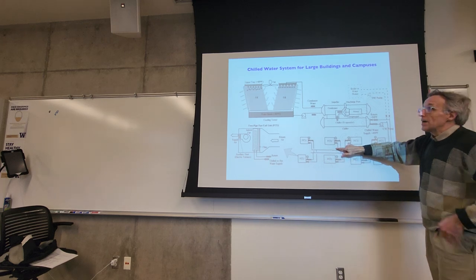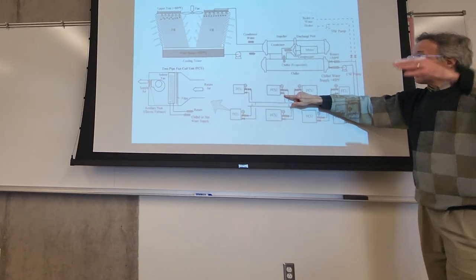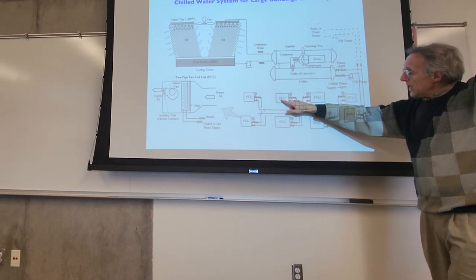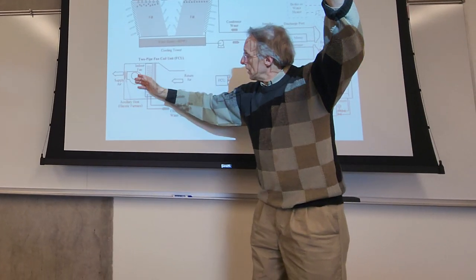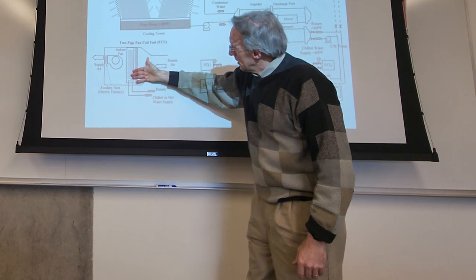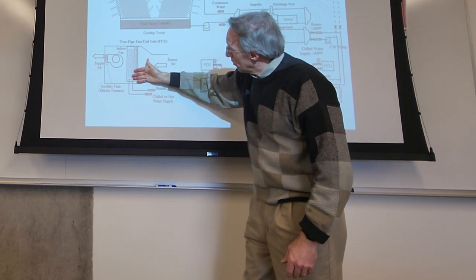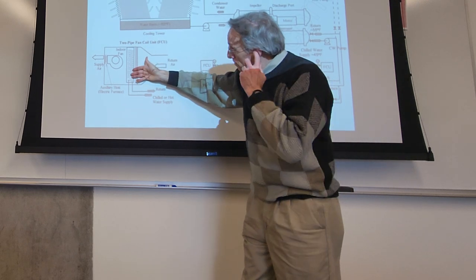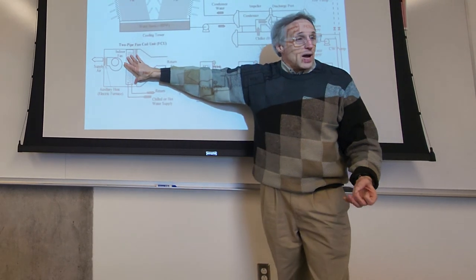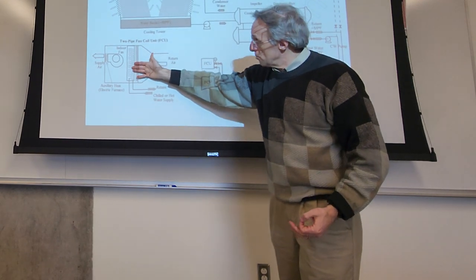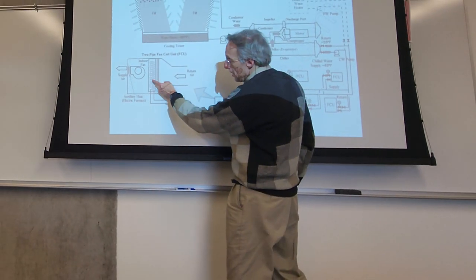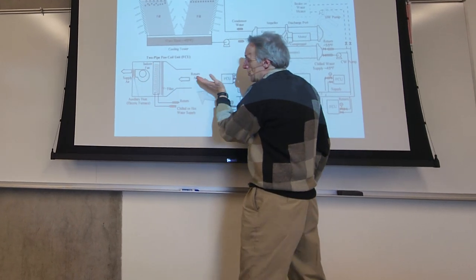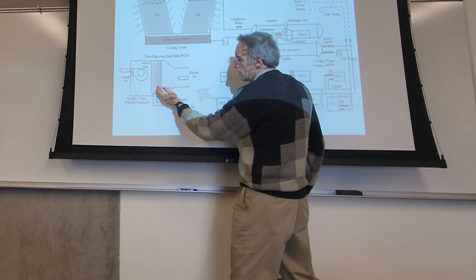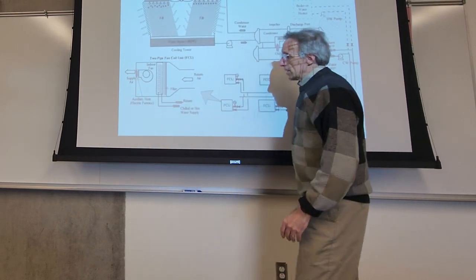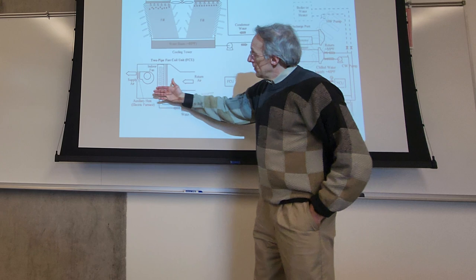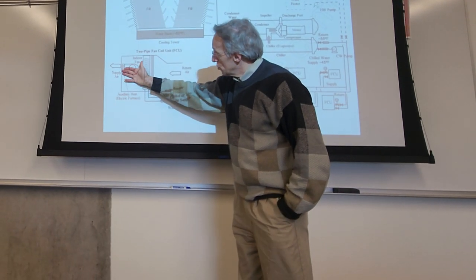And then when you have a building space, you put a little box above the room that has a fan. This is actually what it looks like. Now you have a cooling coil that has cold water in it. It looks a lot like a refrigerant evaporator, except that you're running cold water through the tubes instead of refrigerant. So the cold water comes in, and you've got a fan that sucks room air in, blows it across the cold water coils, and then out into the space. Some systems also have heating coils as well.